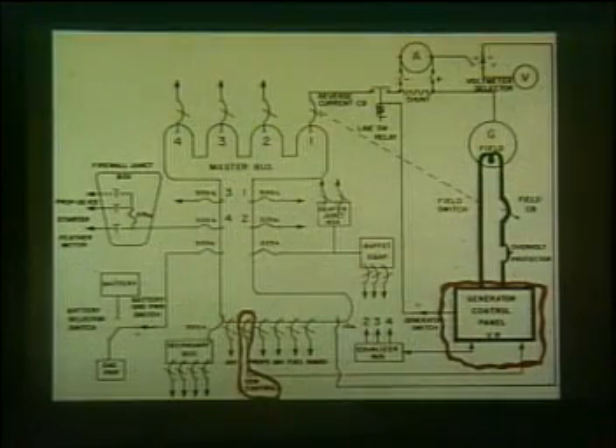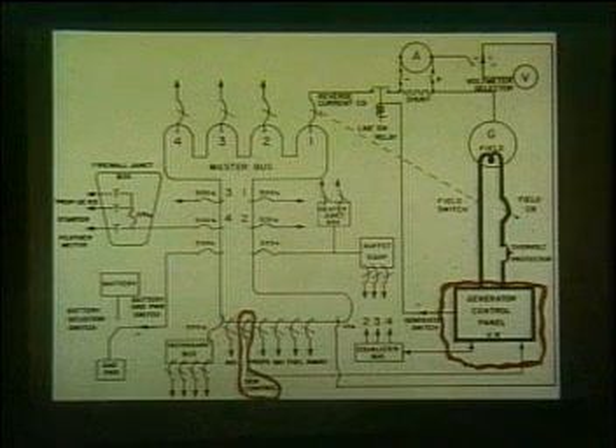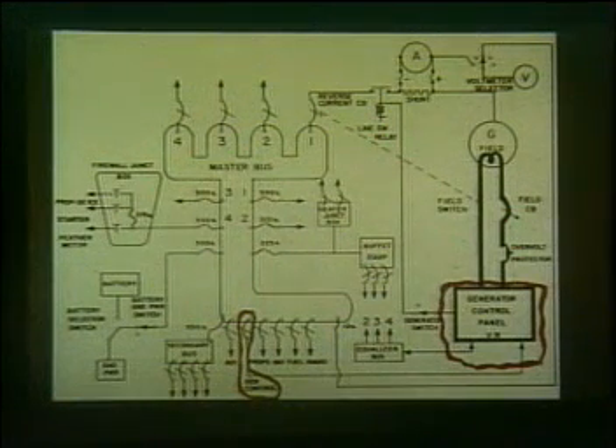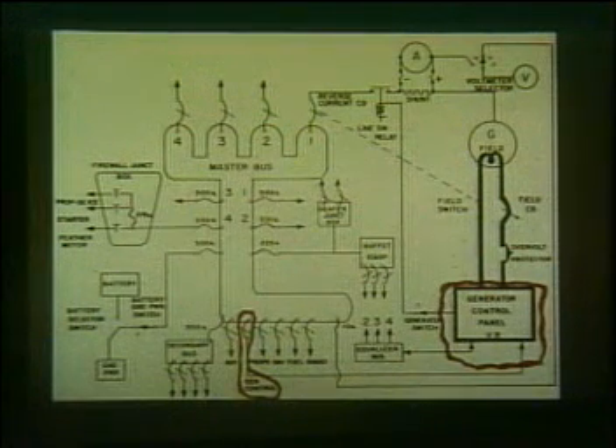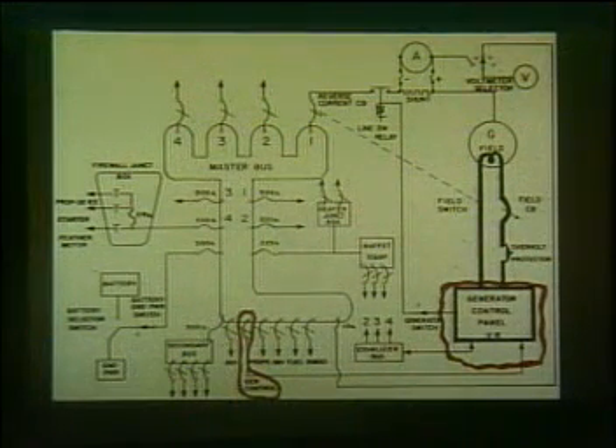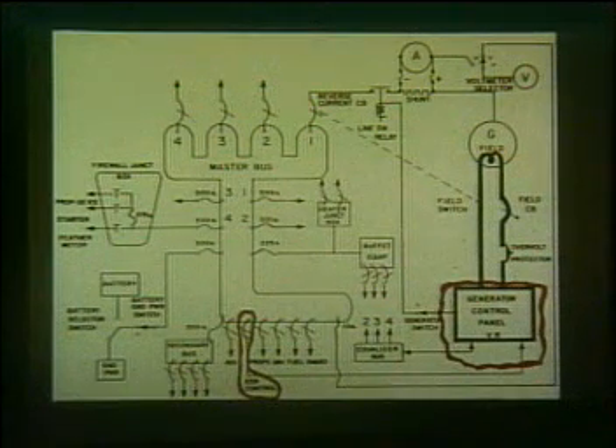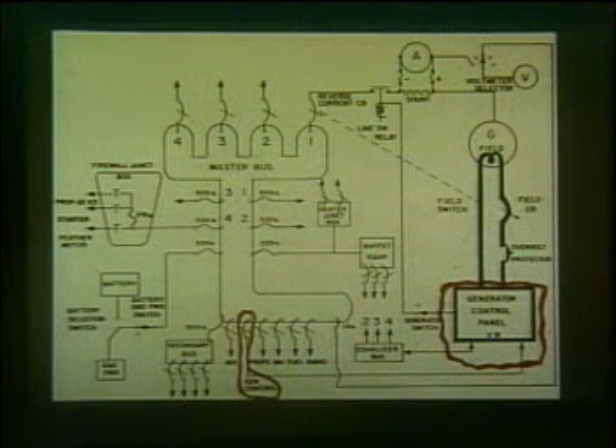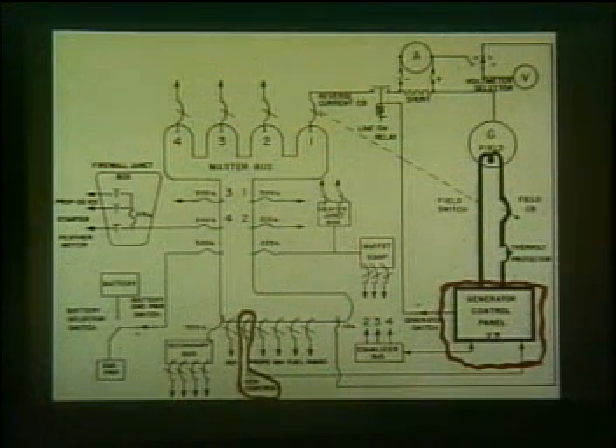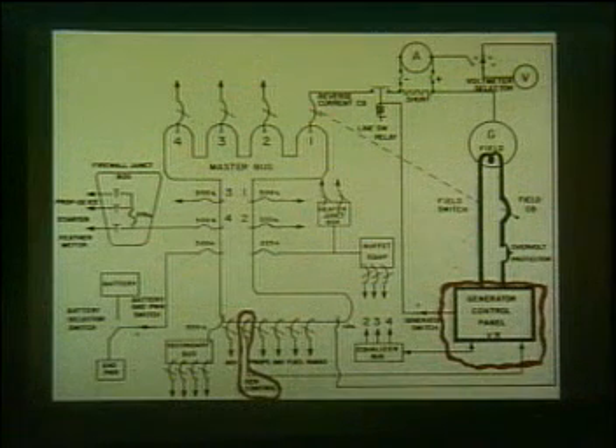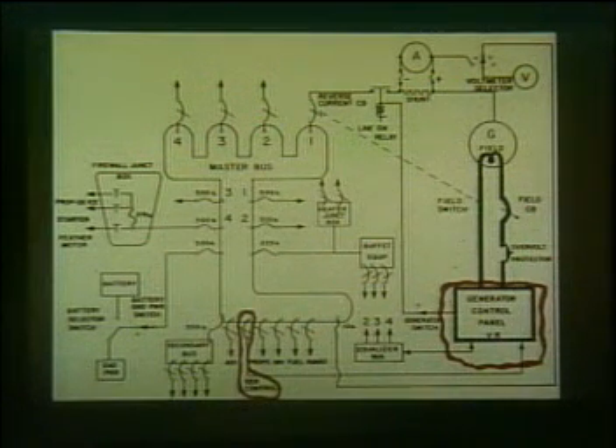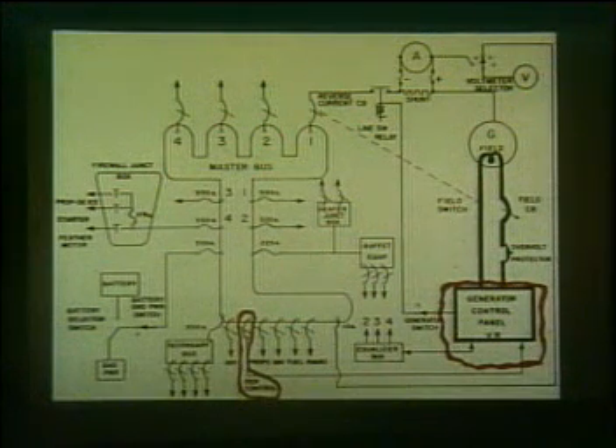The generator field is connected to the generator control panel in the voltage regulator compartment. The generator control panel varies the current flow in the generator field to maintain a constant voltage output. The generator control panel is connected to the master bus through the generator control circuit breaker. This control panel will provide automatic voltage regulation and equalization. It will automatically connect and disconnect the generator to the master bus under all normal operating conditions.